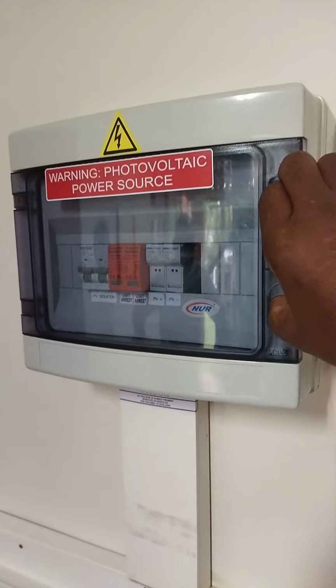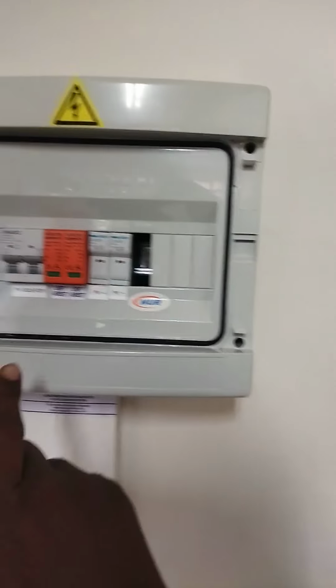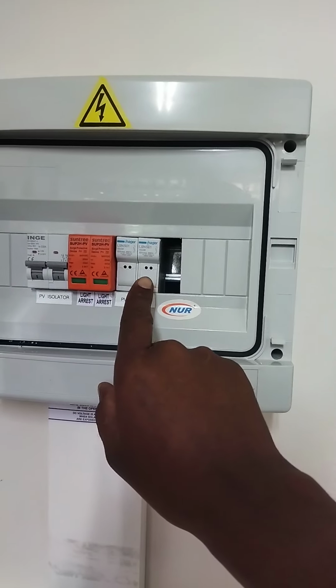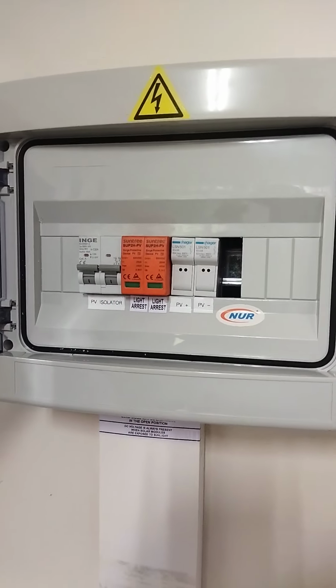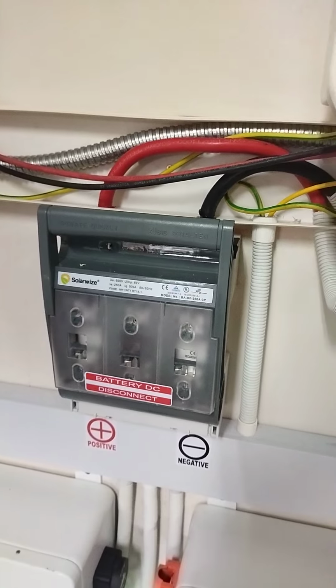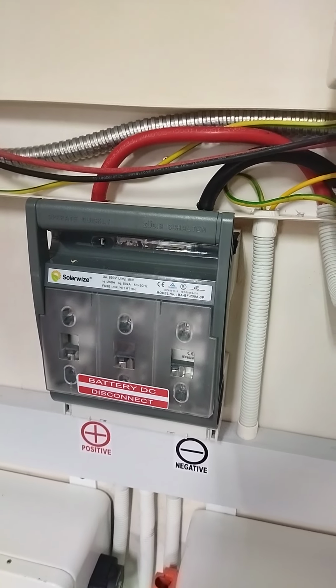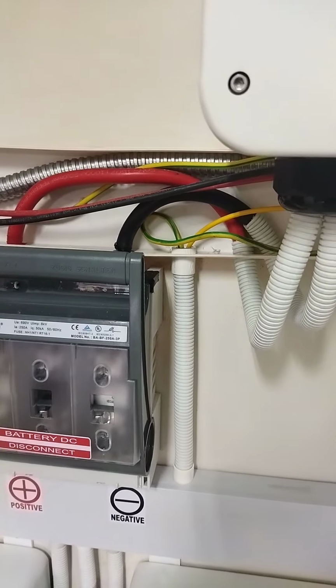The spray pipe you see here is the cable coming in from the PV, crossing over to the combiner box, which is our DC point, the PV combiner box. I've got my 2 PV fuses in there, surge arrestor, and my isolator to isolate for any work we're doing. And then down here for our 8 kilowatts, we're using a 250 amp fuse disconnector with 50 millimeter cables.